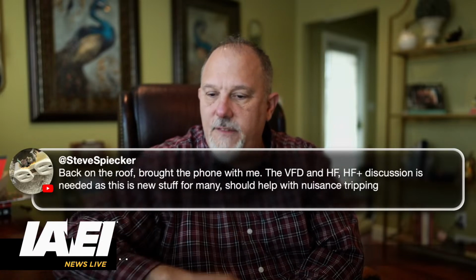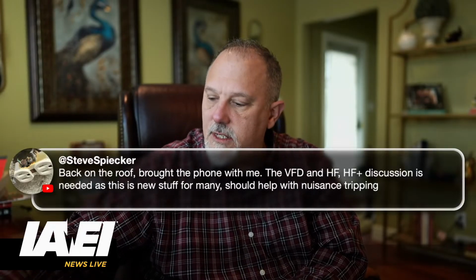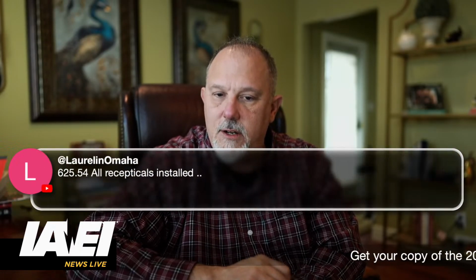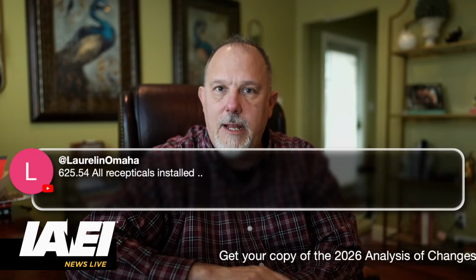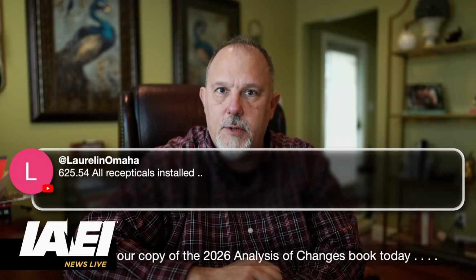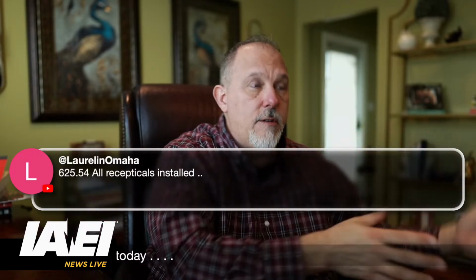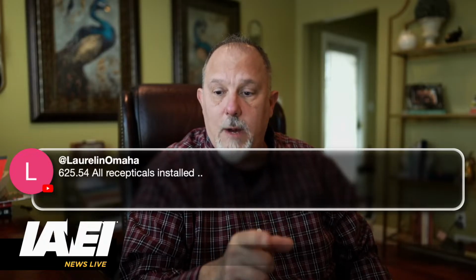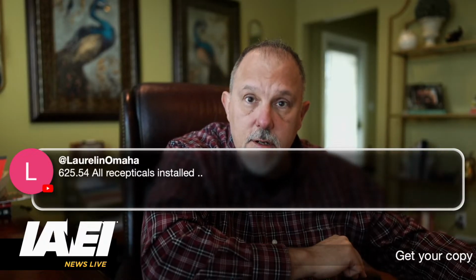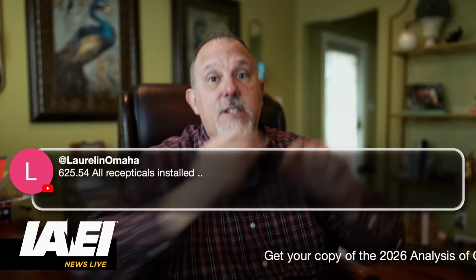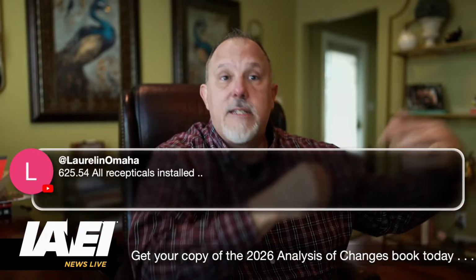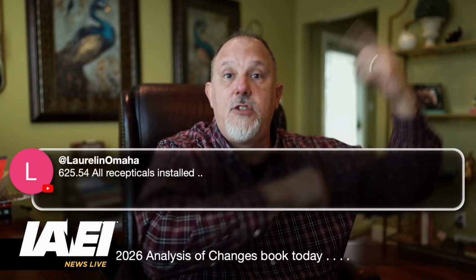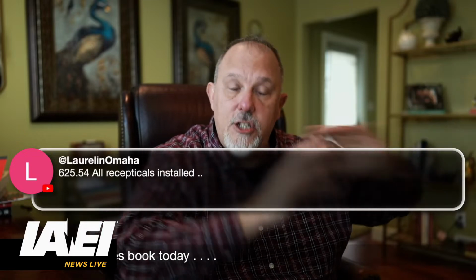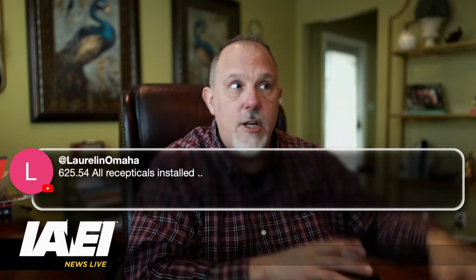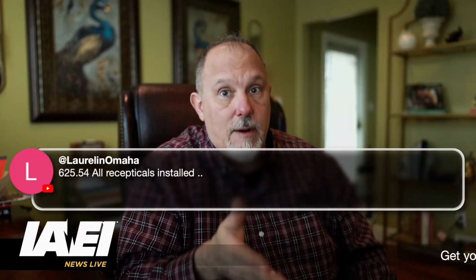625.54 says all receptacles installed, blah blah blah - so 625.54 tells you about cord and plug connected. But because it doesn't say anything about hardwired, that means you're still in 210.8F. Now, if I hardwire in my garage, then I don't need a GFCI, because the garage requirement in a dwelling unit is for receptacles - that's in 210.8A and B. It's just receptacles in a garage. 210.8F applies to outdoor outlets.